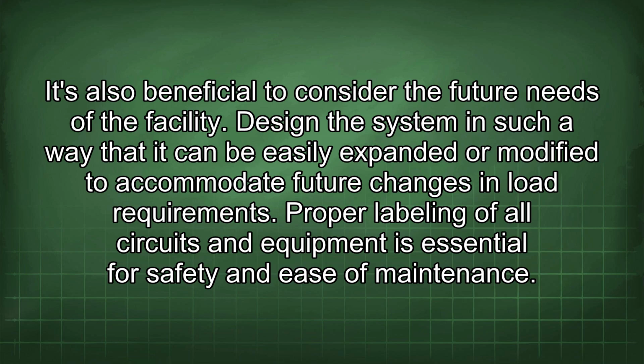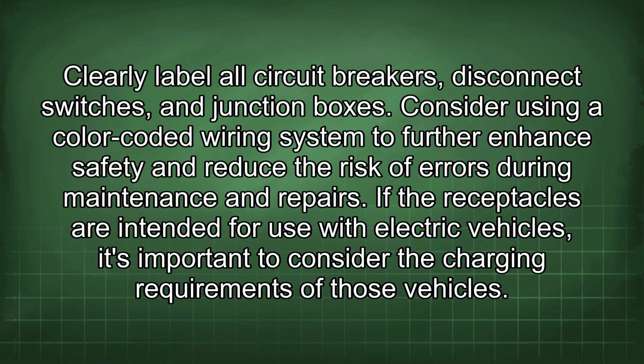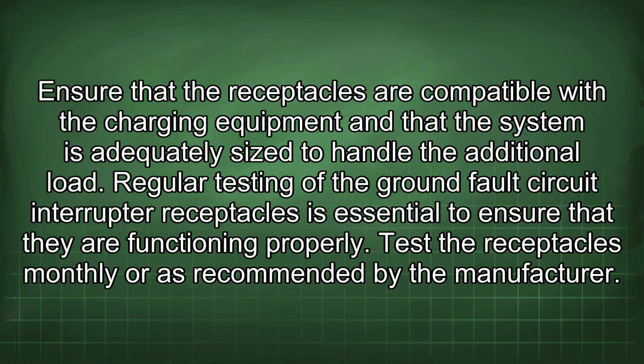Proper labeling of all circuits and equipment is essential for safety and ease of maintenance. Clearly label all circuit breakers, disconnect switches, and junction boxes. Consider using a color-coded wiring system to further enhance safety and reduce the risk of errors during maintenance and repairs. If the receptacles are intended for use with electric vehicles, it's important to consider the charging requirements of those vehicles. Ensure that the receptacles are compatible with the charging equipment and that the system is adequately sized to handle the additional load.